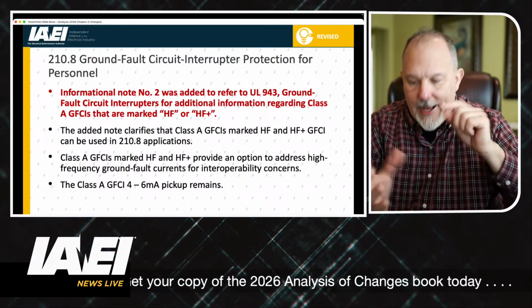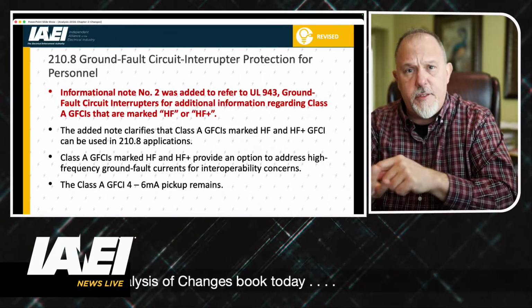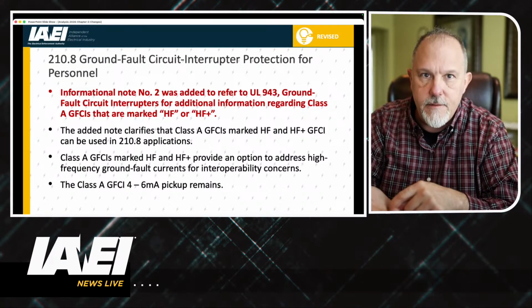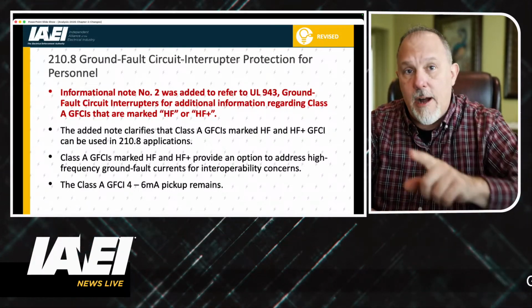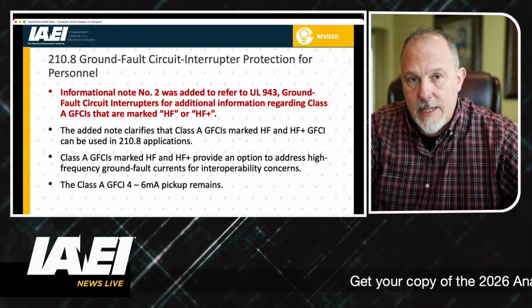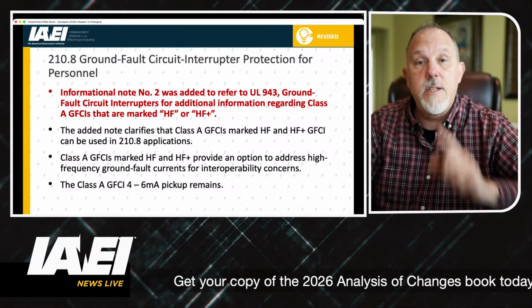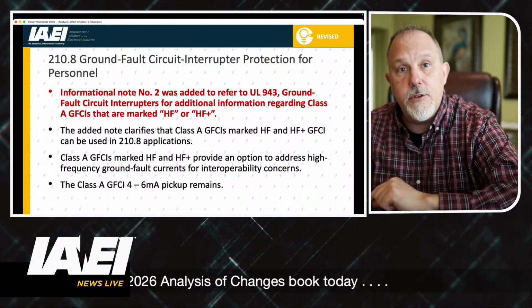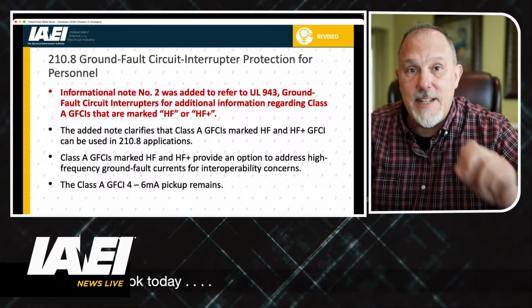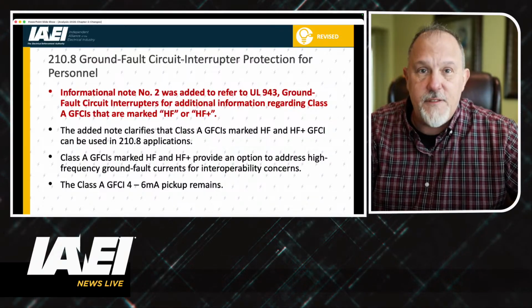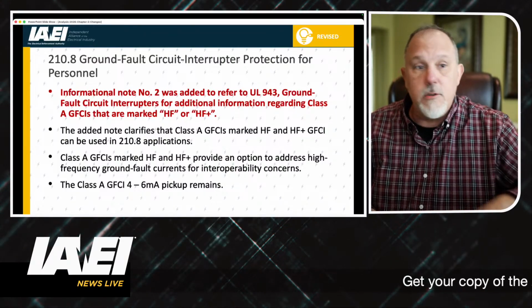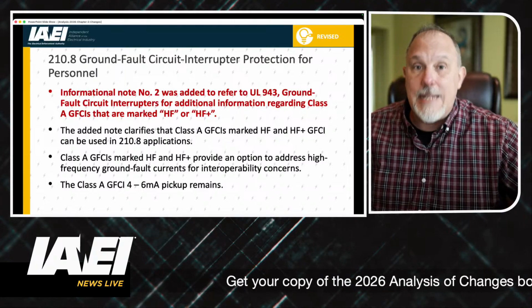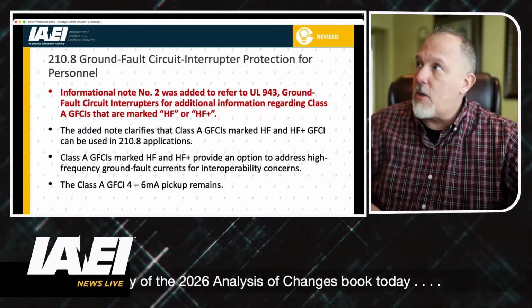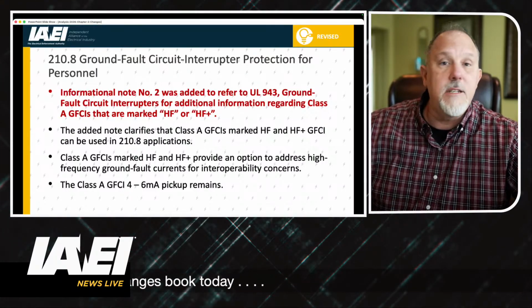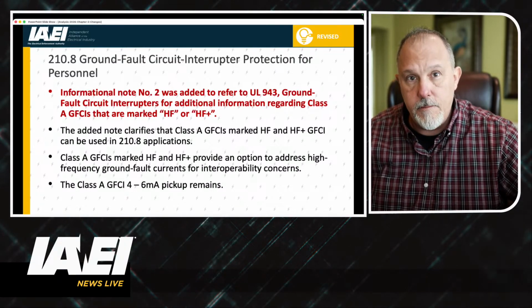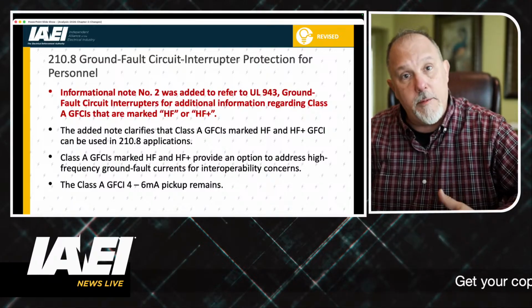It's still a UL 943 GFCI, and it has HF. And you did not enter into the 2026 National Electrical Code yet. You can still apply that device in your circuit because it's still a GFCI. The fact that it's also labeled HF is no different than a receptacle that's also labeled WR or also labeled TR. I can use a tamper-resistant receptacle in my attic, in places where it's not required by the code, because it exceeds the fundamental requirement.